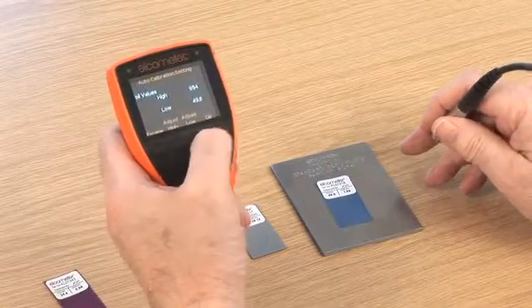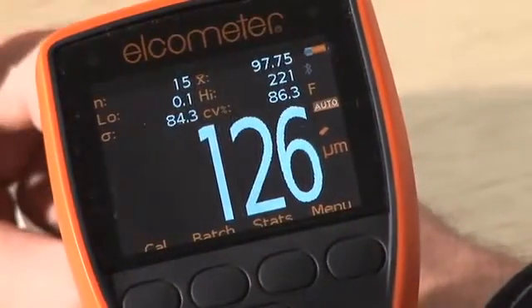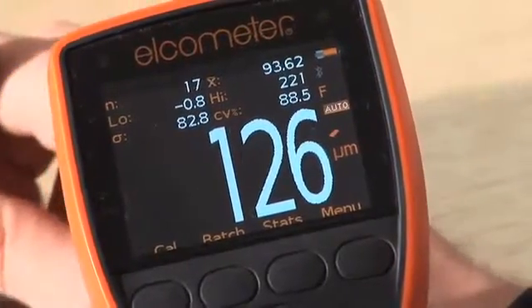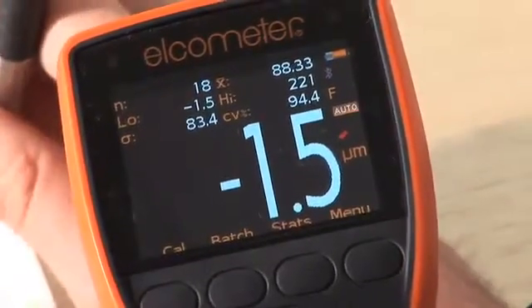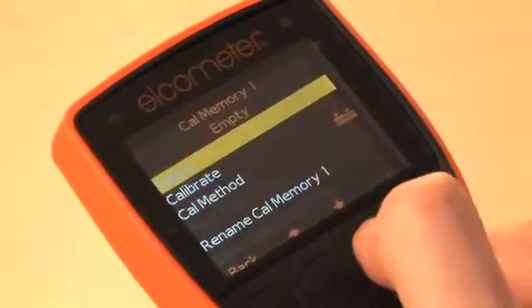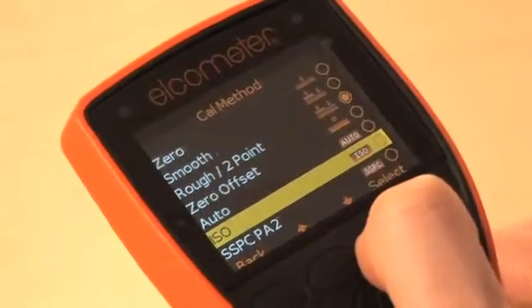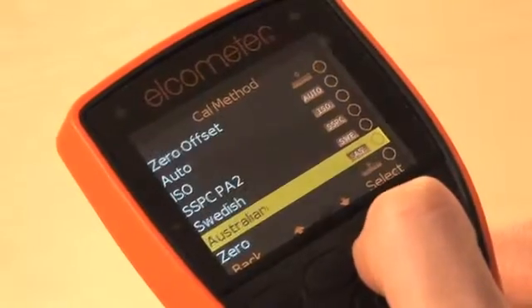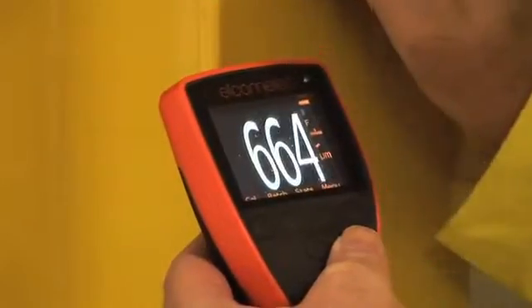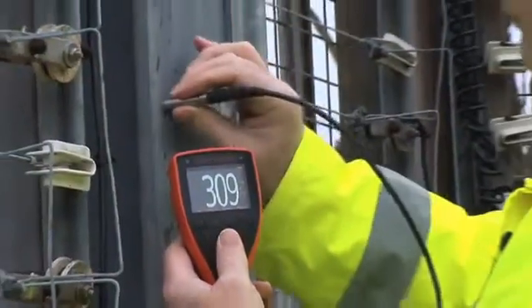The Elcometer 456 Model T gauge has a special calibration check feature which, when enabled, displays the out-of-calibration icon on the display screen when a reading is more than 10% outside the calibration foils used with the calibration routine. Elcometer S and T models have four additional predefined calibration methods included for ISO, SSPC-PA2, Swedish and Australian standards. These not only define the calibration method to be used, but also set up the data collection method as defined by the appropriate standard.